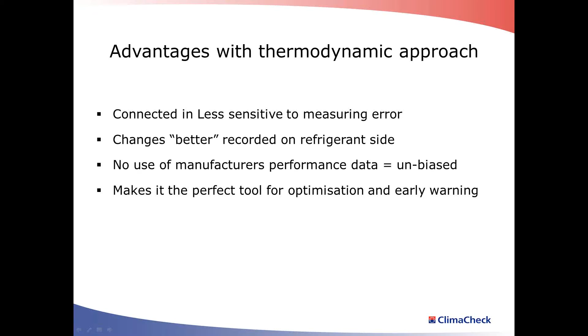And another advantage is, of course, that you don't only see the total performance, you also see the performance of all components in the system, which makes it much easier to see what's happening. And if you do some changes, you can immediately see the improvement in the system. And of course, it's nice not to have to use any manufacturer data for the system. And this becomes a very efficient tool for optimization and early warning. If, for example, your compressor is losing isentropic efficiency, you know immediately that you need to deal with that.